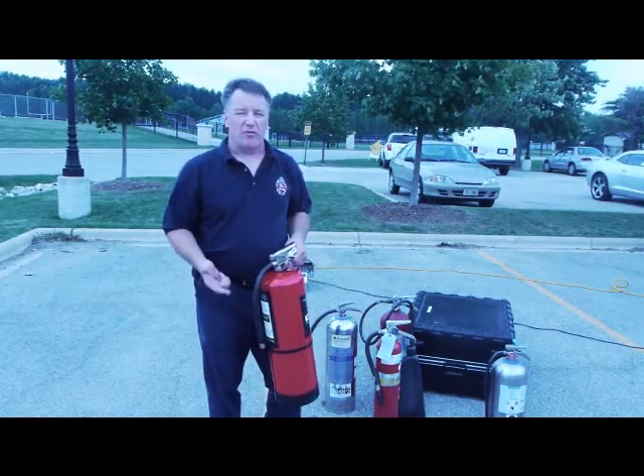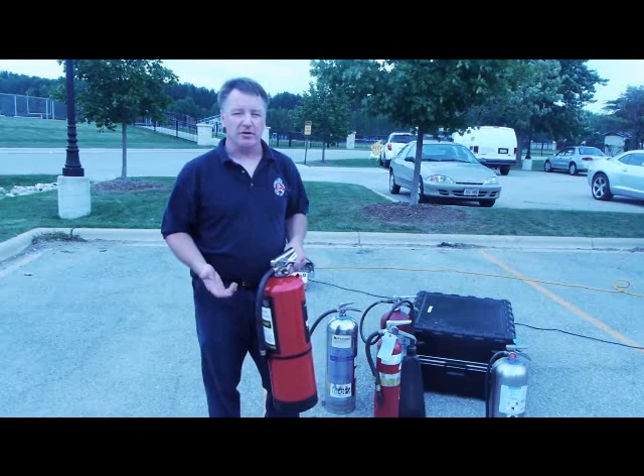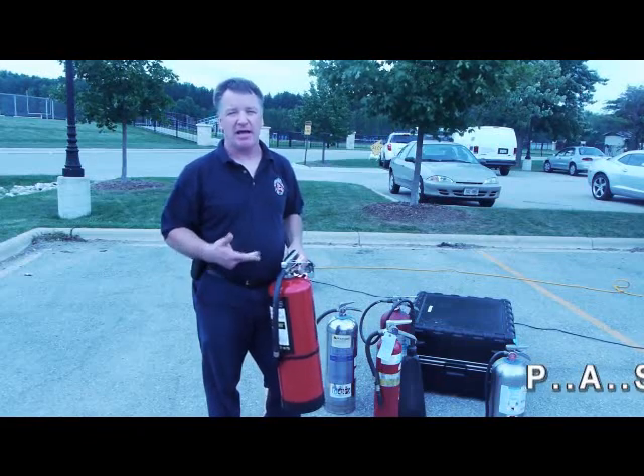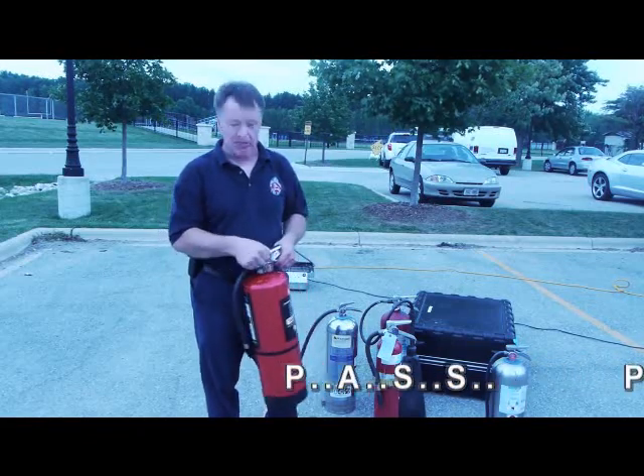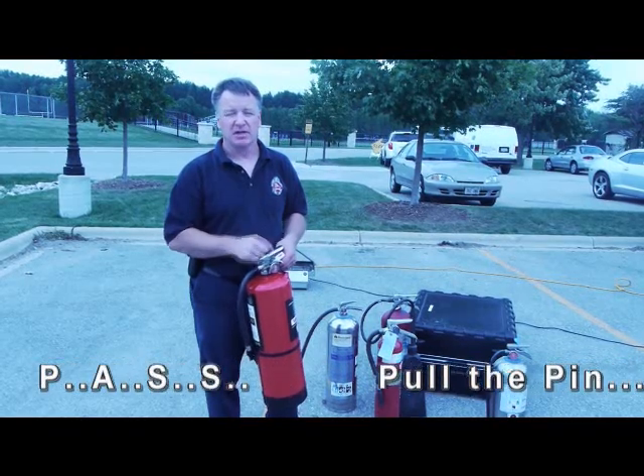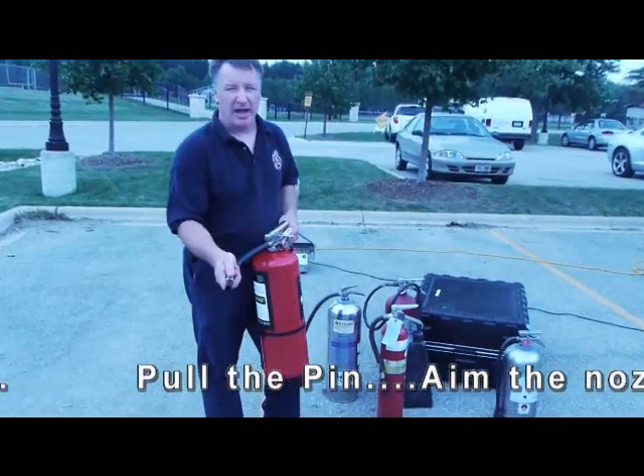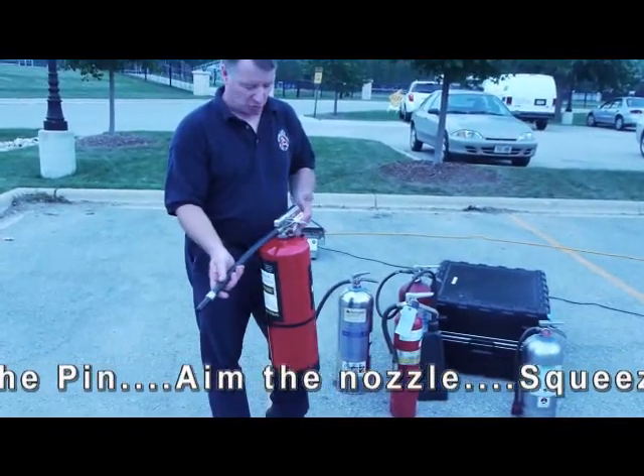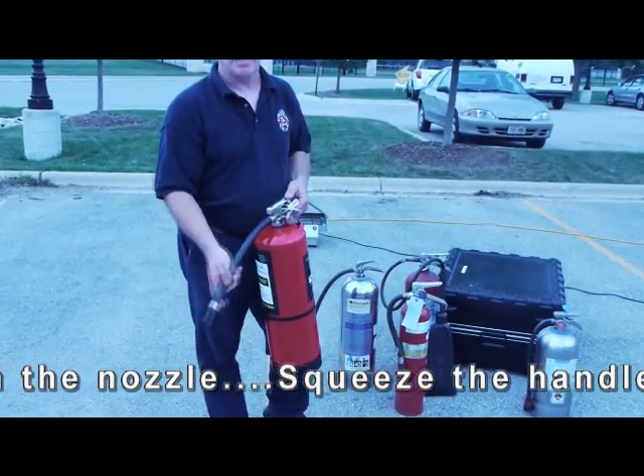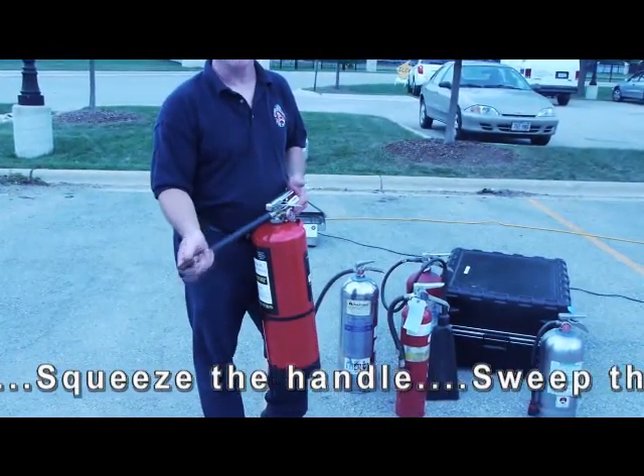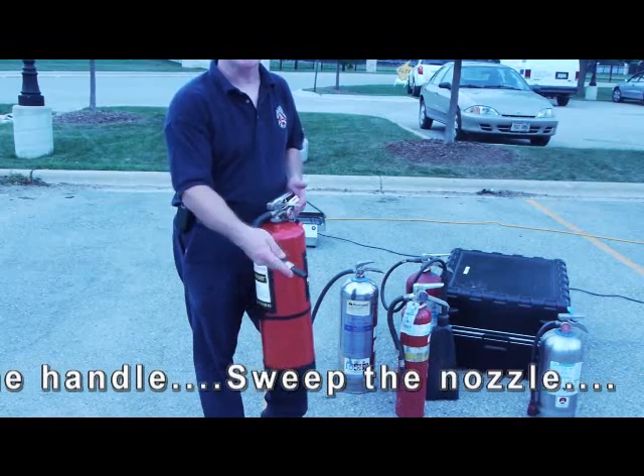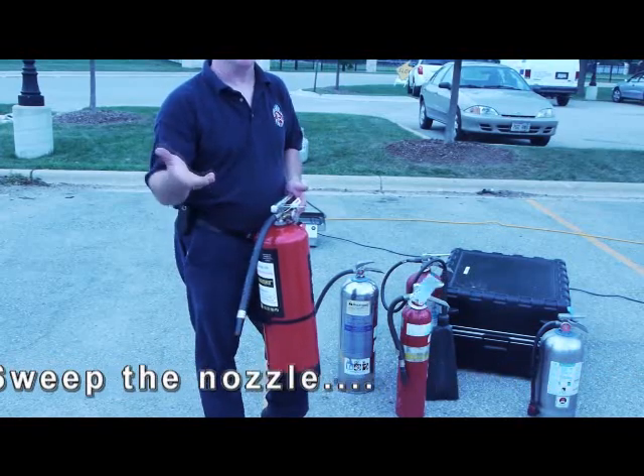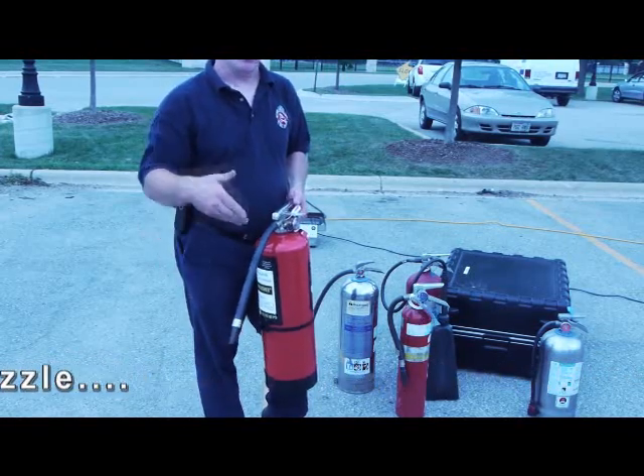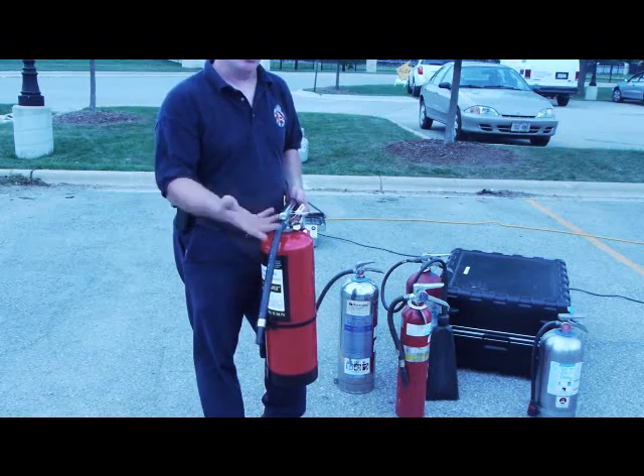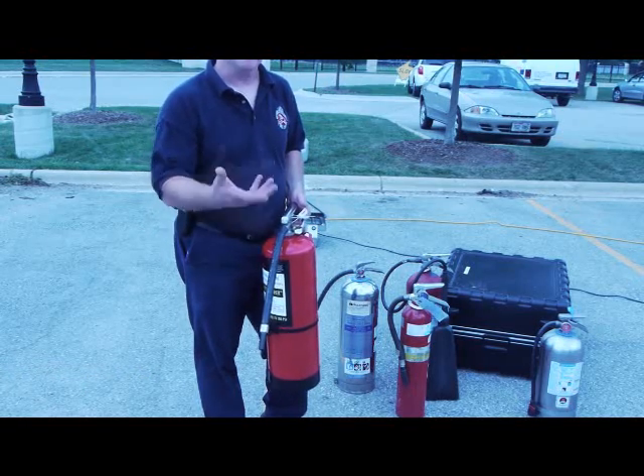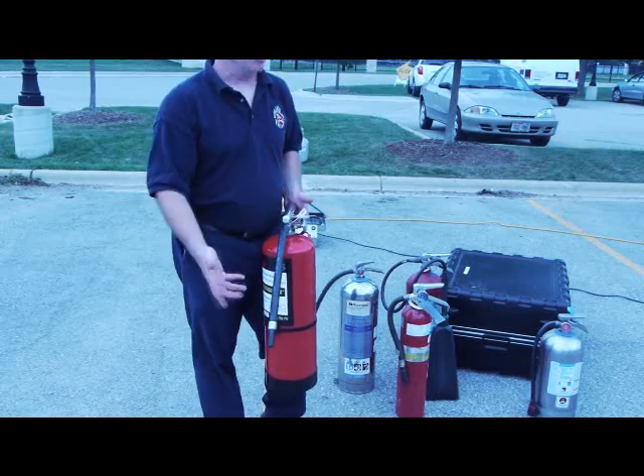What you want to remember for putting out a fire is the acronym PASS, P-A-S-S. Pull the pin so that it releases the levers, aim the nozzle at the base of the fire, and then squeeze the levers tight to let the agent expel from the nozzle, and then sweep across the base of the fire. And you want to be aiming at the base of the fire so that the extinguishing agent cools or covers or eliminates the oxygen from that combustion process.